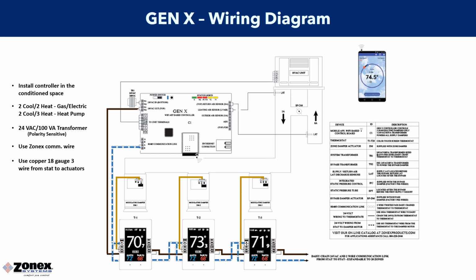The Zonex controller is also supplied with 2 sensors. One of them is your leaving air sensor. This sensor should be installed in your supply plenum before your bypass. The sensor is critical to the operation of the system and is utilized for staging as well as capacity control. There is also a return air sensor that should be installed into your return air duct to give us readings on your mixed air. When wiring up your Zonex controller to your rooftop unit, you'll be using 18-7 or 8, and you will just match up the terminals accordingly to your rooftop unit's operation. So R to R, Y to Y, W1, W2, G.